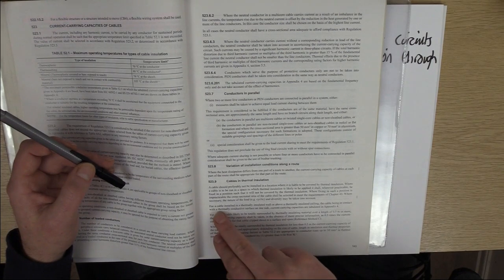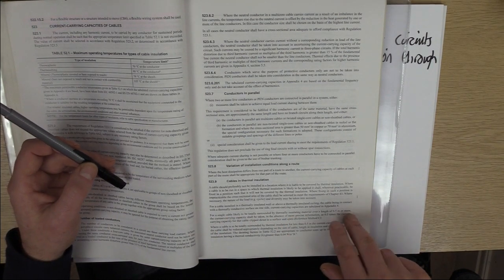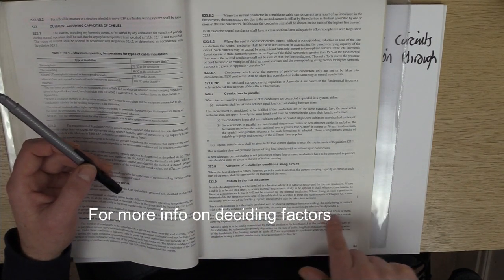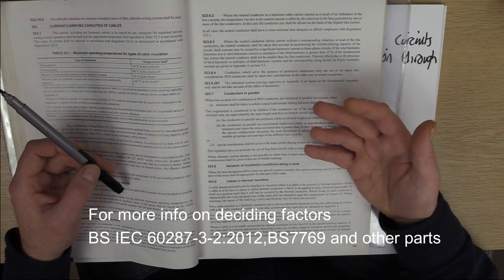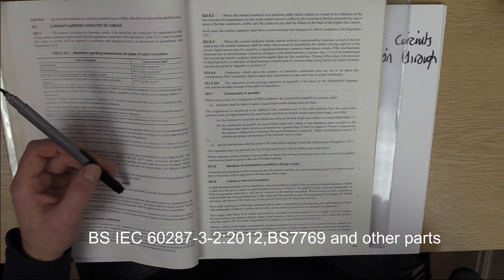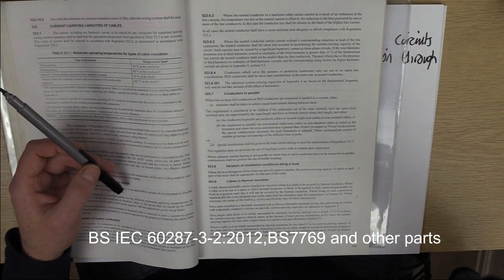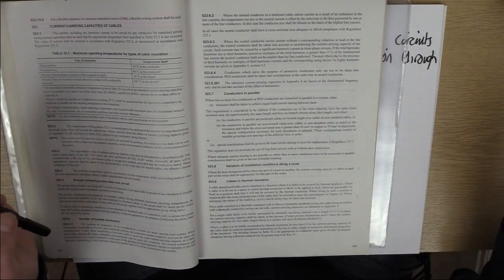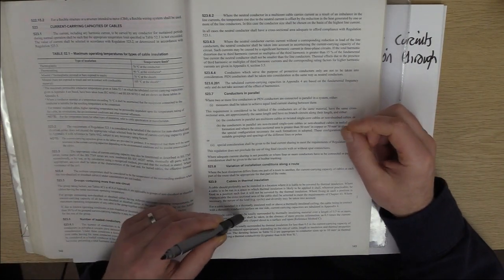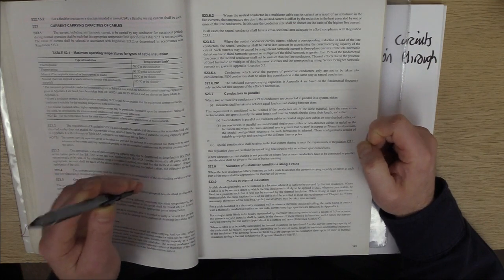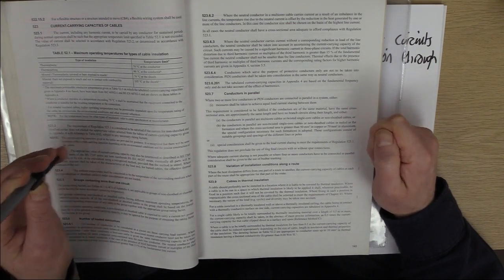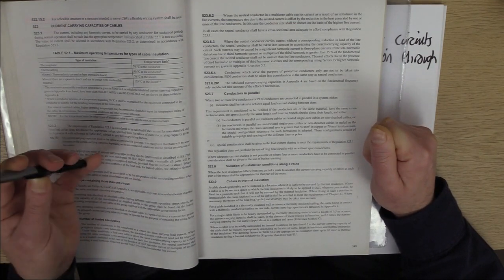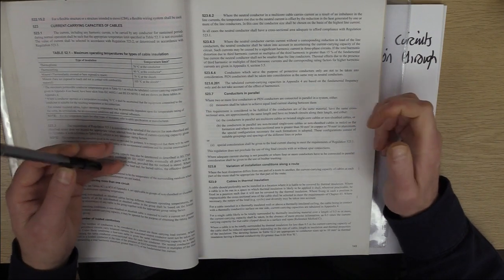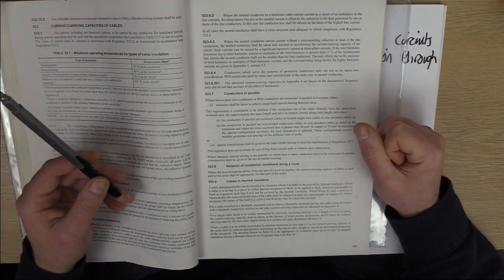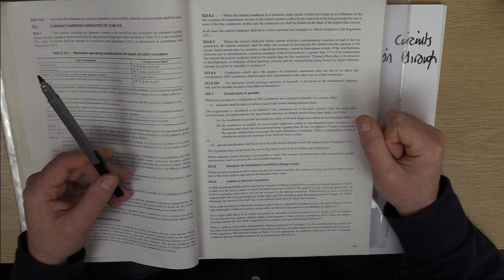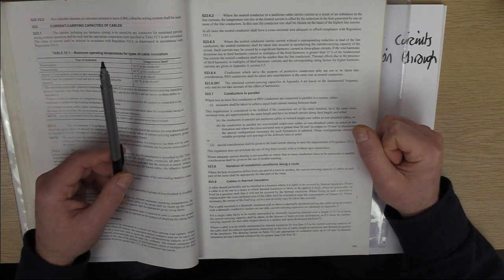And you keep reading down here, and it essentially says if your single cable is likely to be totally surrounded by thermal insulating material over a length of 0.5 metres, so just 500 mil, the current carrying capacity should be taken in the absence of more precise information as 0.5 times the current carrying capacity. So it halves the current carrying capacity, which basically means we're going to have twice the cross-sectional area.